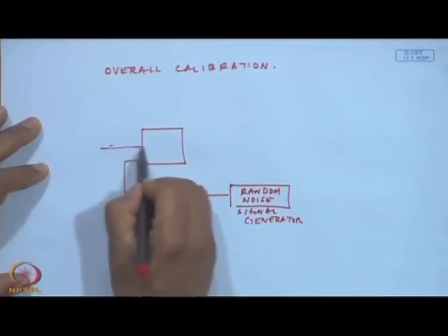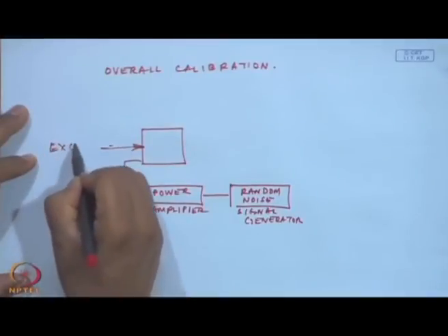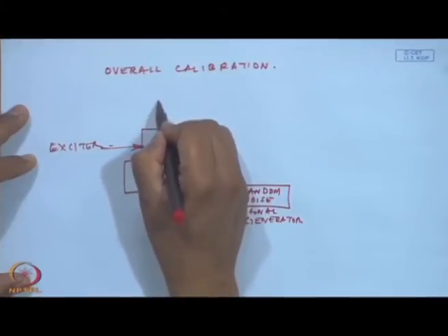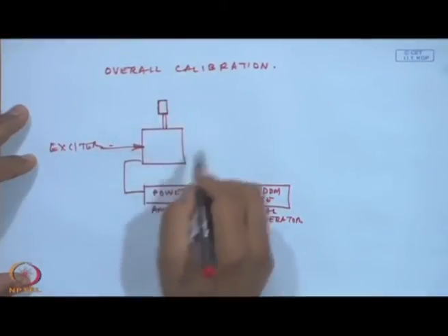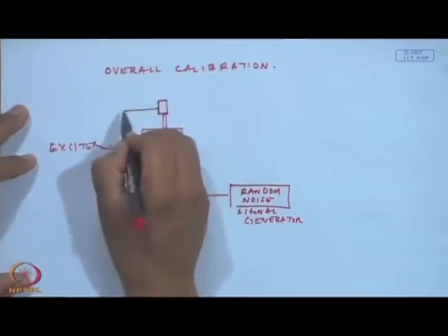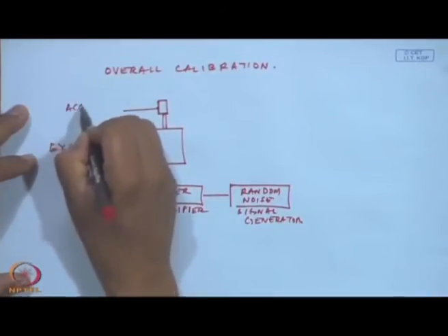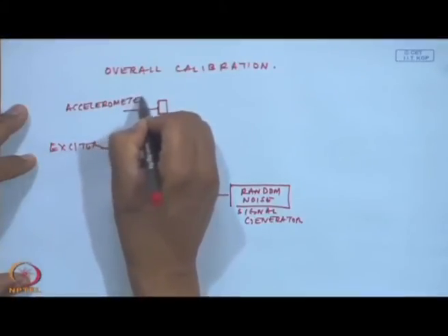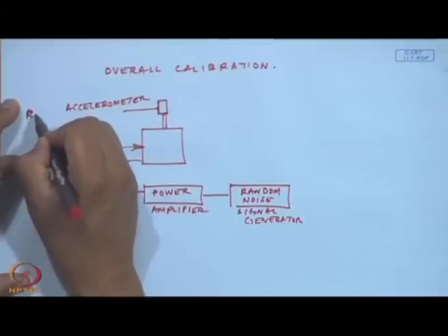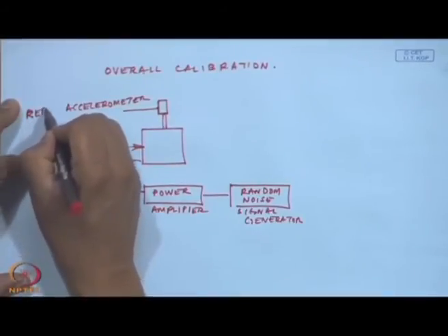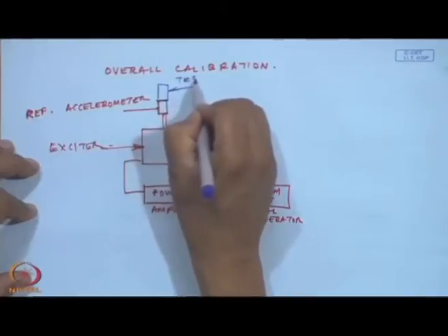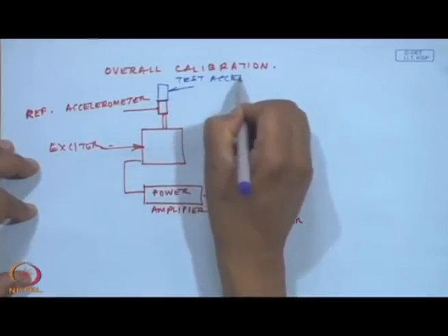This is an exciter, and onto this you attach an accelerometer, which is a reference accelerometer, onto which we measure the test accelerometer.